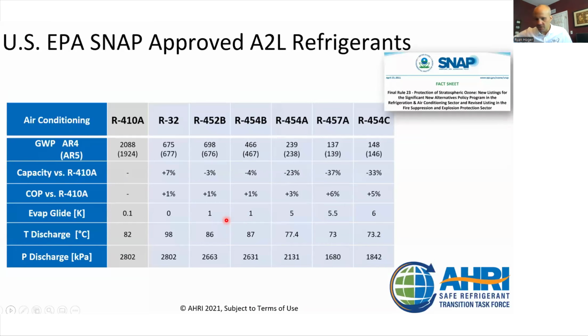All right, if we look at a few of these side by side, we'll look at 410A, R32, and 454B. We will ignore the other ones because no one's using them, so they do not matter to us. Obviously, 32 and 454B are below the 700 global warming potential limit. R410A was three times the limit, hence the reason why it's leaving.